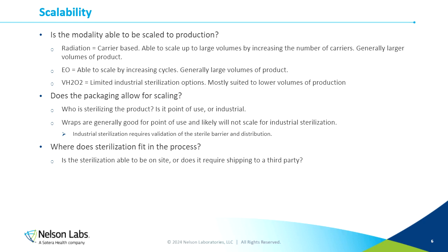So consider who's going to be sterilizing it is also going to help you consider other items, such as what does your packaging configuration need to be, as well as what sort of validation work do you need, distribution testing, shelf life, things of that nature. So the question comes down to, where does sterilization fit in the process? Is the sterilization able to be on site? Is that going to be something that you can do in line with production? Is sterilization going to be contracted out to a third party and provided on an industrial level? Or is the expectation that sterilization is going to be conducted and performed by the point of use, such as the hospital or clinic that is sterilizing the device?